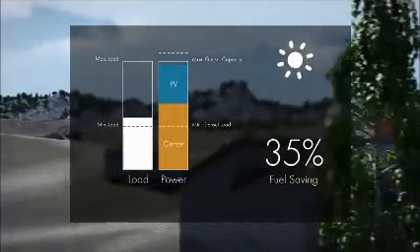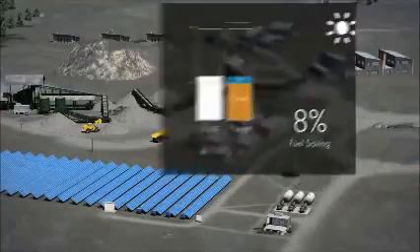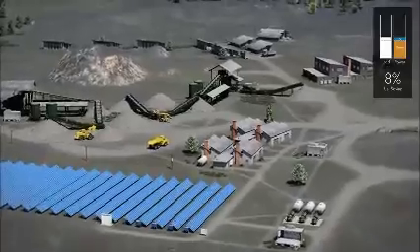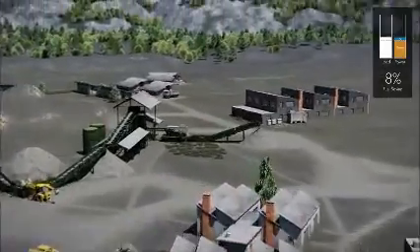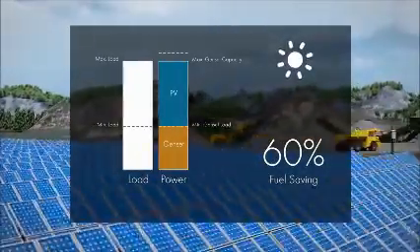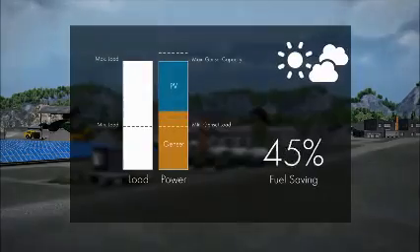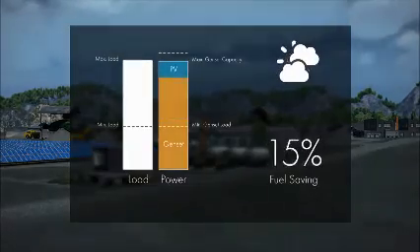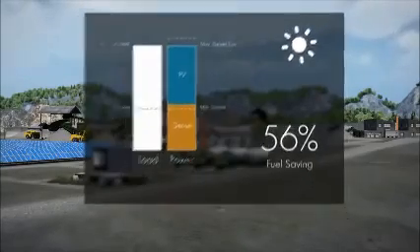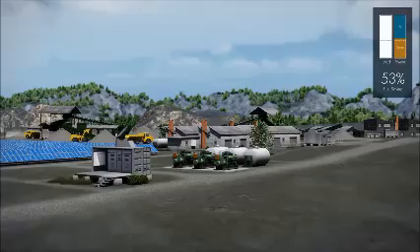If sudden load changes occur, the hybrid system reacts instantaneously. If necessary, the PV power will immediately be throttled down to guarantee smooth genset operation and optimum grid stability. If heavy loads are immediately switched on, the system reacts flexibly to these load changes. If it becomes cloudy and photovoltaic power drops, grid stability is protected. The SMA Fuel Save Controller continuously accounts for sufficient spinning reserve of the gensets.